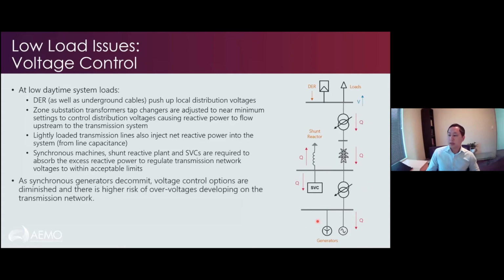Now, what's happening though is as the synchronous generators decommit, we're having less and less options for controlling and absorbing reactive power in the system, and we're at higher risk of over voltages in the transmission network. We're already seeing over voltages occurring in the distribution network, and every now and again we are seeing some voltages creep up to higher levels in the transmission system.